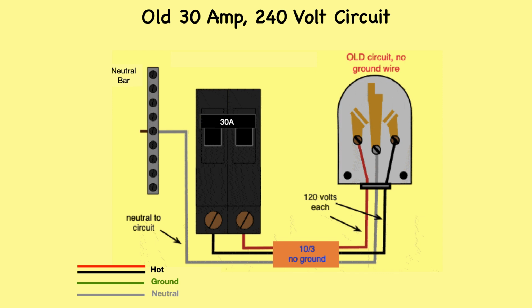This wiring is for a 30 amp circuit breaker, serving a 30 amp, 240 volt receptacle. The 10-3 cable for this circuit has 3 conductors and no ground. A 30 amp circuit like this may be found in older installations, for example, clothes dryers, or maybe a kitchen cooking range.